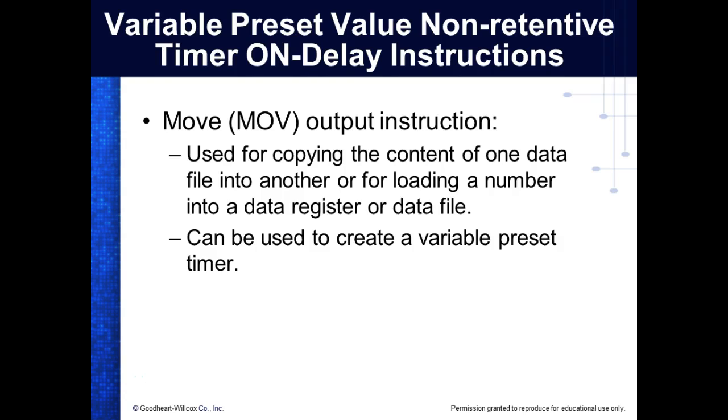The Siemens is understood to be milliseconds. But if you end the time with an S, it's understood to be what? Seconds. So if you don't specify S, if you don't say 100 S, then it considers it to be milliseconds. So you can do that. I think Step 7 is always milliseconds. The new TIA Portal allows you to enter seconds or milliseconds. Are we okay?